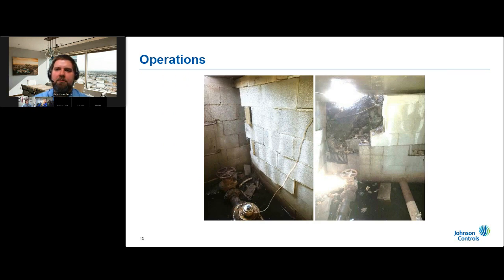Here are photographs from a large meter vault that is about to collapse in on itself. Frankly, I was stunned — not just because the vault was caving in, but because I would never have gotten into that vault myself. When those cinder block walls finally buckle and fall, both the meter setting and the bypass lines will very likely be crushed. Even if a street valve is found and service is quickly shut down, this will be a very expensive emergency repair requiring heavy equipment. An annual large water meter inspection would have caught this problem early when the walls could have been shored up properly.